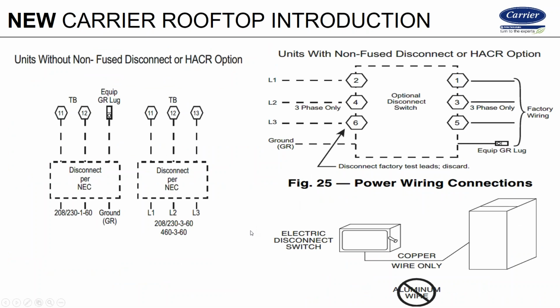A lot of you will like this. We now have a connection in the unit. We've got a terminal block for L1, L2, L3. There's no more wire nutting wires together and putting 2 on the contactor and 1 on the fan contactor. That's gone. We actually have a terminal block on here.